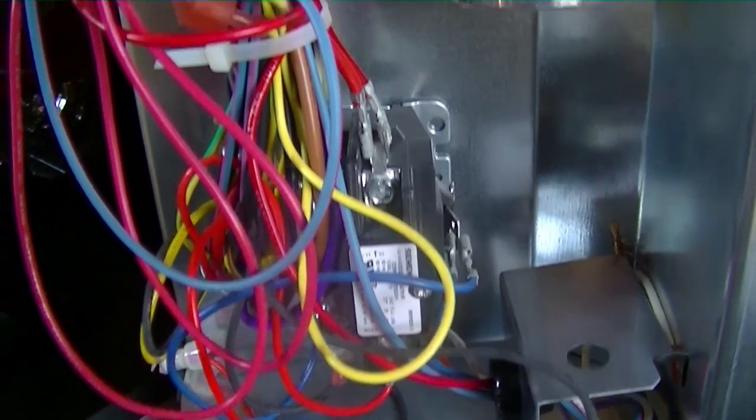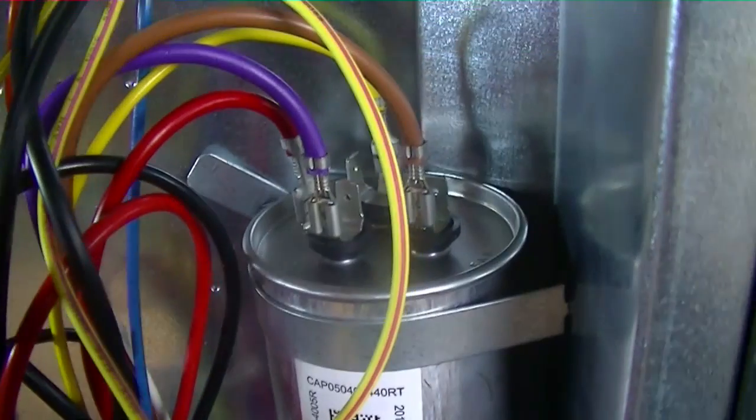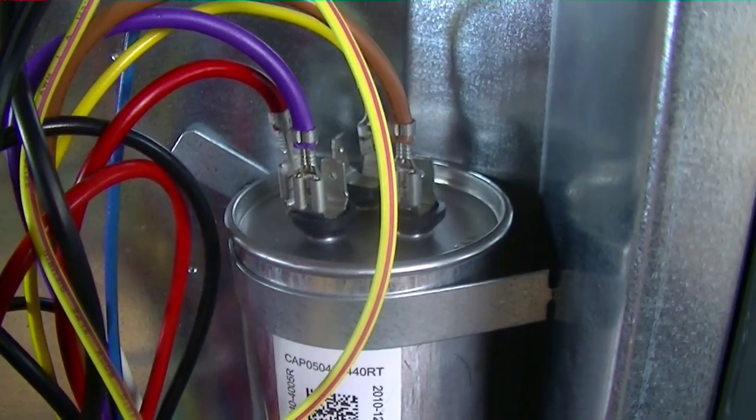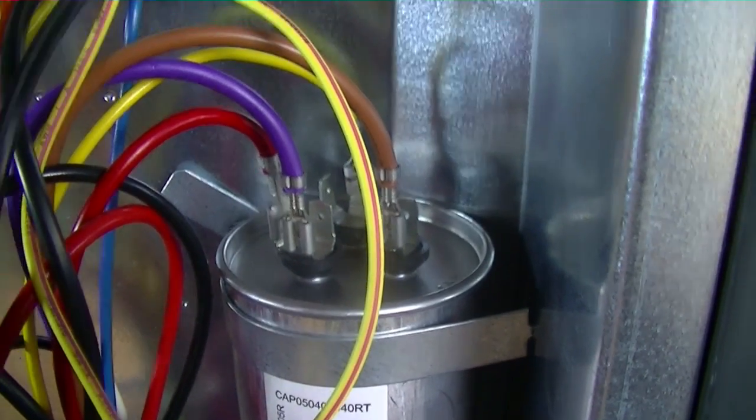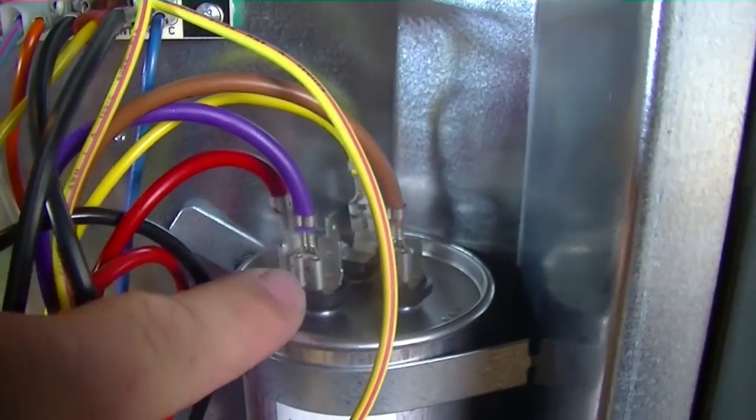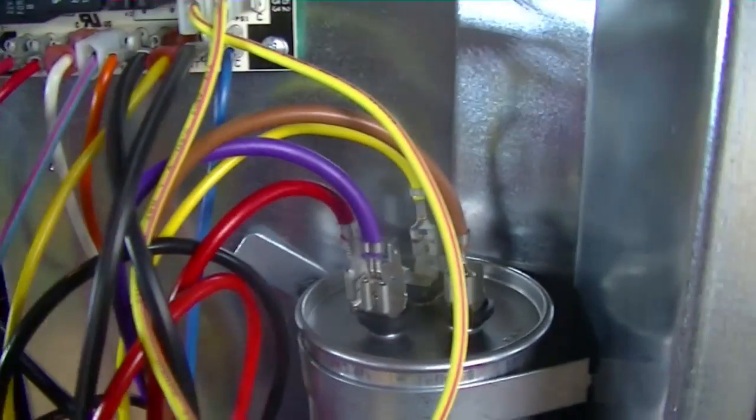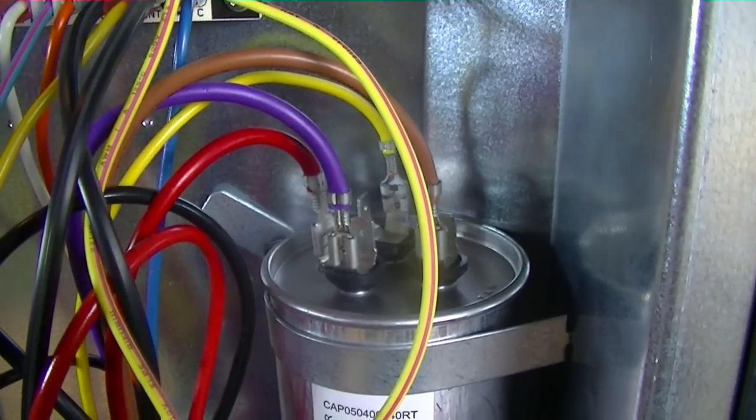The run wires will go to the common on the dual run capacitor. But we can only see two wires on that common terminal. Our purple goes to the fan motor. The purple carries one half of the voltage, 120 volts.